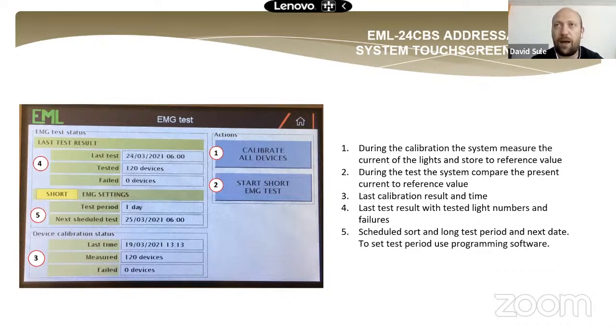When we test the light's status, it's testing the communication of the light and testing the LED, but it's run from the DC 32 voltage when we have AC, and we can set up a long test that will be a battery capacity test. It can be 30 minutes and up to 3 hours. We can set this up to automatically test for different test period times.